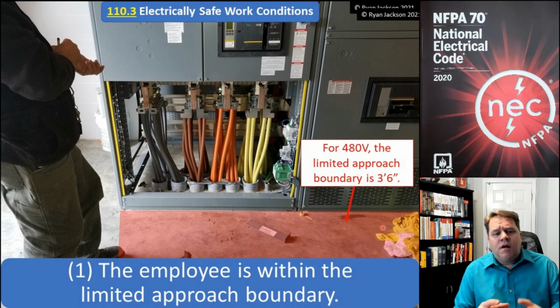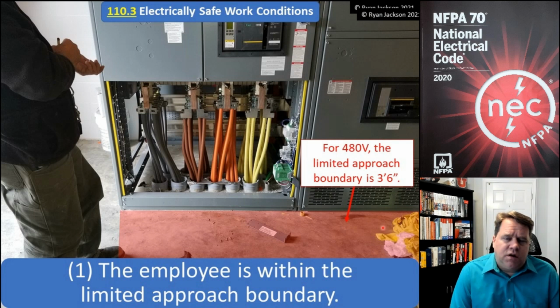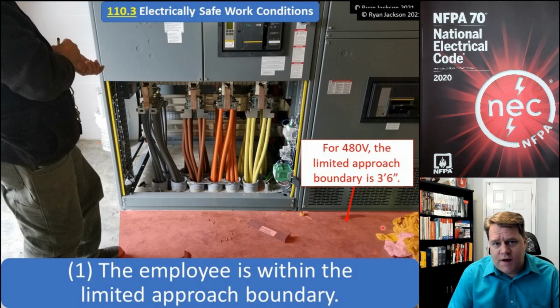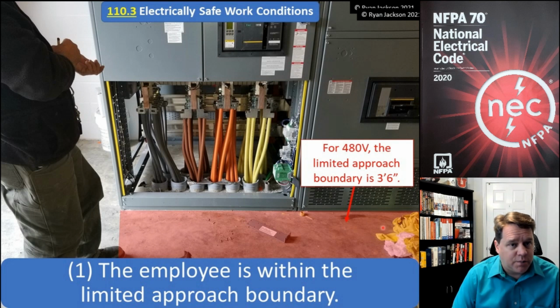Okay, so we have a couple of different boundaries in NFPA 70E. One is an arc flash boundary, and that's how far away from a potential arc flash source you would need to be in order to avoid a second-degree burn. We have the limited approach and we have the restricted approach. The restricted and limited approach both have to do with shock protection, and that's what we're talking about here.